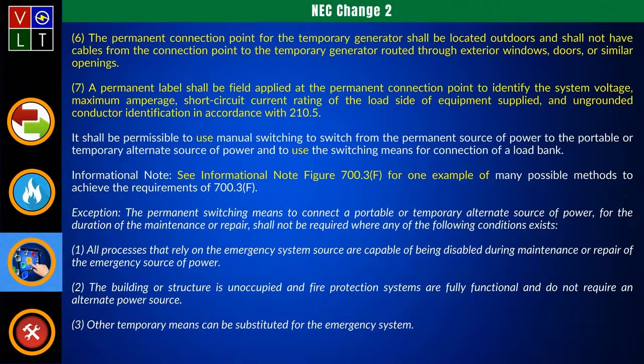And then you also need to have what else? A permanent label shall be field applied at the permanent connection point to identify the system voltage, the maximum amperage, the short circuit current rating of the load side of the equipment supplied, and ungrounded conductor identification in accordance with 210.5.